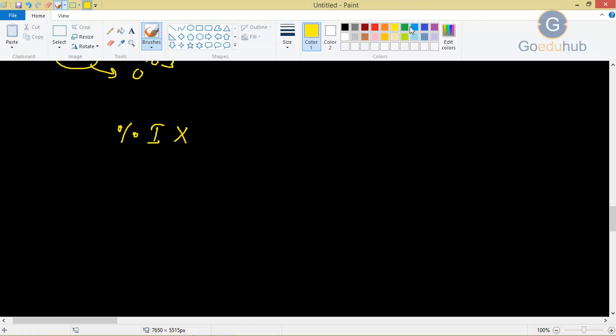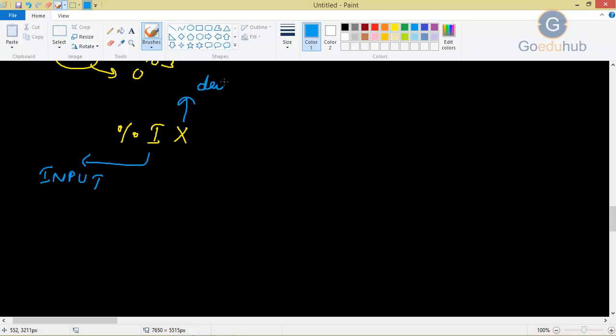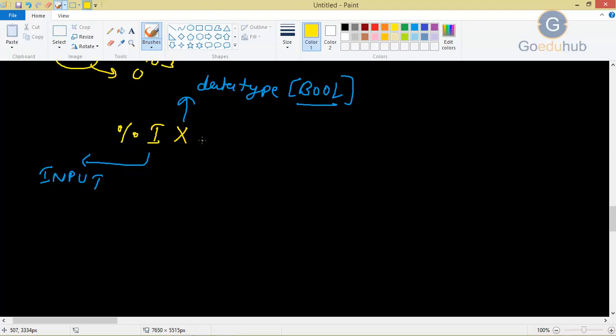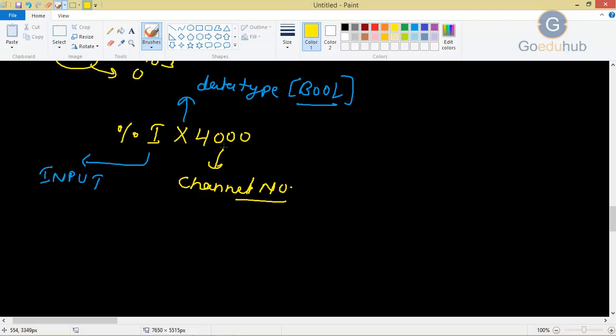As you know, I will represent your input, then X will represent your data type. The data type we are using here for digital inputs will be your bool. Then after %IX, you have 4000 — this is your channel number. In one channel, as I already told you, for boolean operations we require one bit, and in one channel we have 8 bits. So for the first input, your address will be channel number then bit number. The bit number for the first input will start from 0.0.